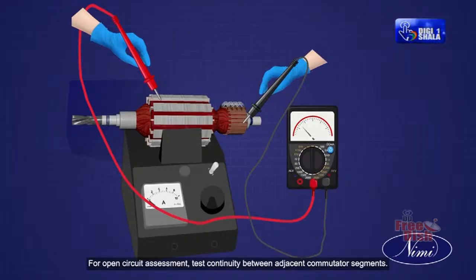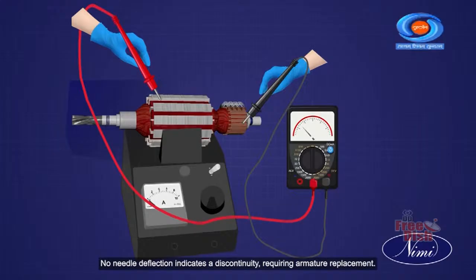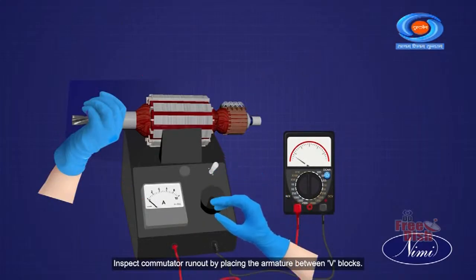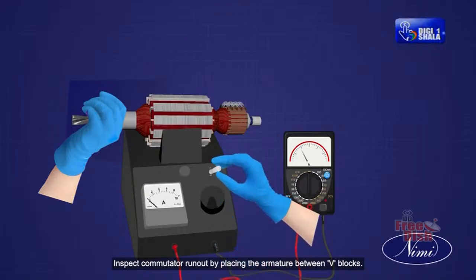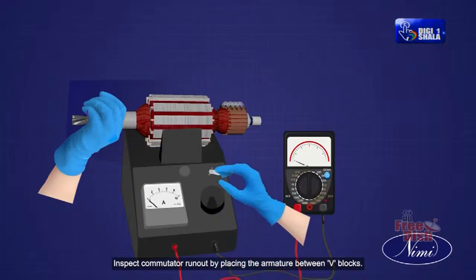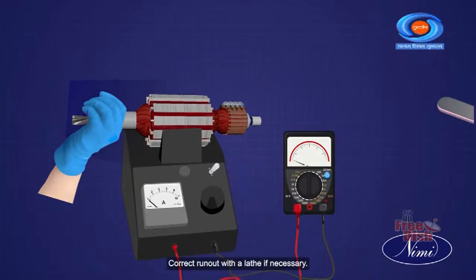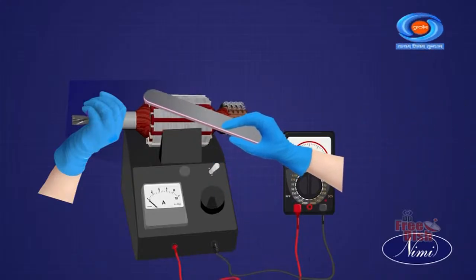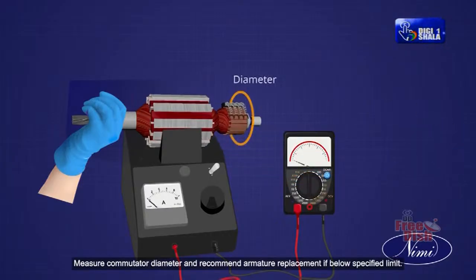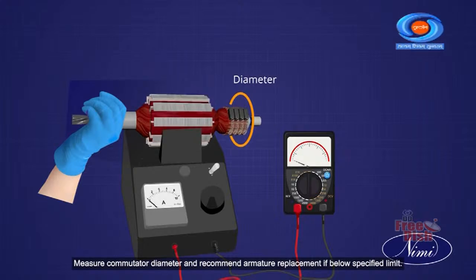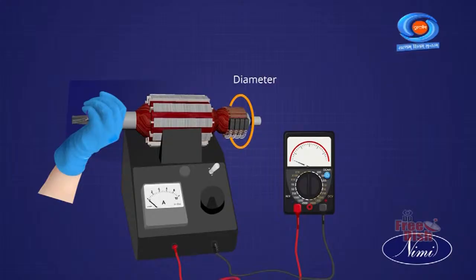For open circuit assessment, test continuity between adjacent commutator segments. No needle deflection indicates a discontinuity, requiring armature replacement. Inspect commutator runout by placing the armature between V blocks. Correct runout with a lathe if necessary. Measure commutator diameter and recommend armature replacement if below specified limits.